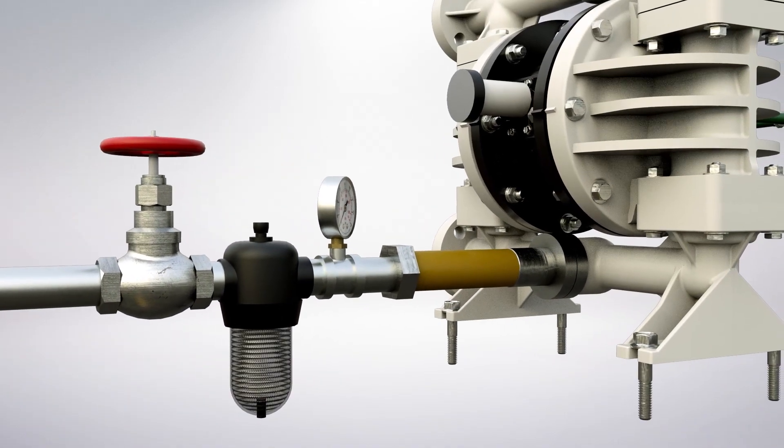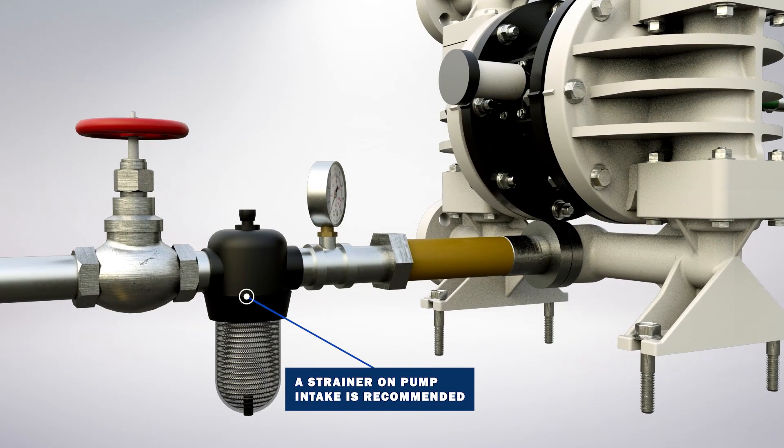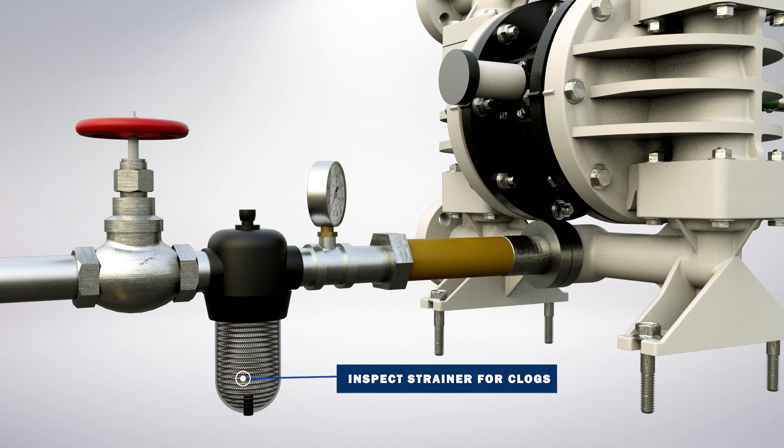While all pumps can pass solids, you should use a strainer on the pump's intake to ensure that the pump's rated solids capacity is not exceeded. Periodically inspect the strainer for clogs. Clogs can lower performance and accelerate diaphragm wear.